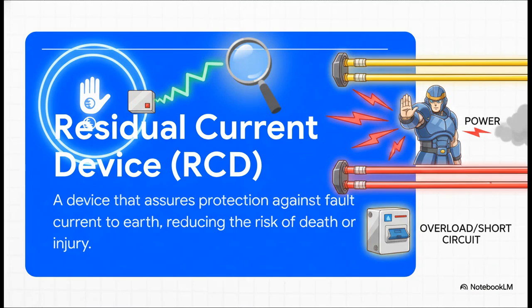Okay, so here's the core idea. An RCD is a safety switch built to do one thing and do it incredibly well. It spots an imbalance in the electrical current. It's so important to get this. It's not looking for overloads or big short circuits. That's a job for a circuit breaker or a fuse. No, an RCD is looking for a leak.